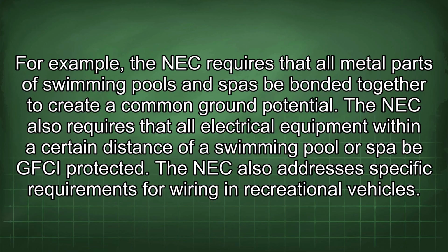For example, the NEC requires that all metal parts of swimming pools and spas be bonded together to create a common ground potential. The NEC also requires that all electrical equipment within a certain distance of a swimming pool or spa be GFCI protected.